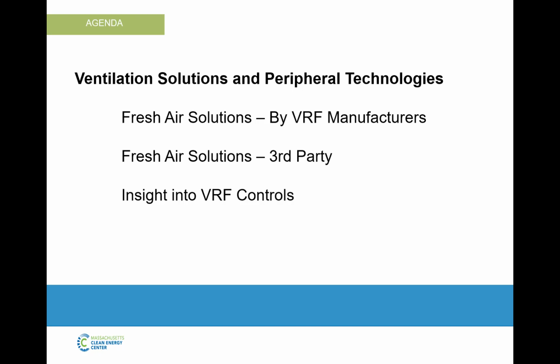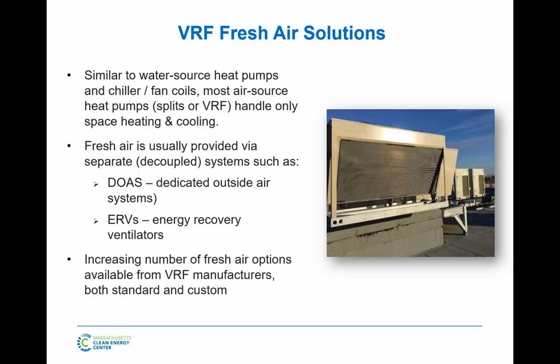So I made a comment earlier about how do you do that. PTACs can bring in fresh air directly. There's certain systems that can, like a VAV system, a package rooftop VAV system will also handle fresh air directly and all that. So there are systems that can do it. A lot of the systems that we compare these to, like water source heat pump, chiller fan coil systems, all need a certain other method of fresh air.